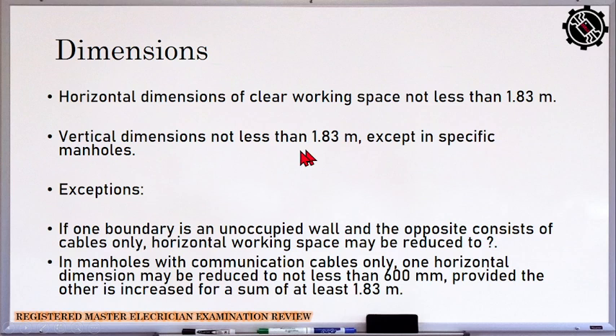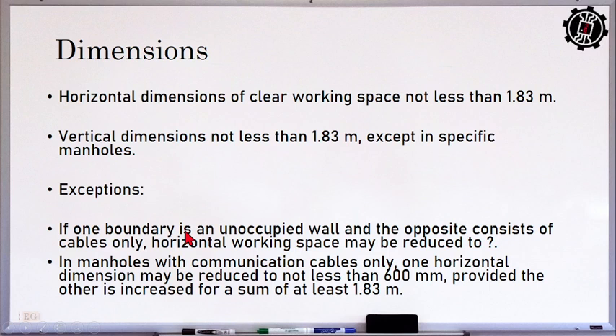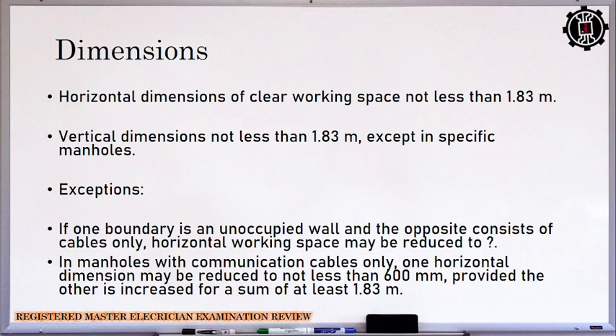Okay, the dimension. So the horizontal dimension of manhole, no, the clear working space shall not be less than 1.83 meters. The vertical also shall not be less than 1.83 meters except in a specific manhole. So the exception is if one boundary is an unoccupied wall or the manholes with communication cables only. So pwede na siya na not less than 600 mm ang kanyang horizontal. Tapos provided na yung kanyang sum is at least 1.83 meters. No? Yung kanyang overall perimeter is not less than 1.83 meters.